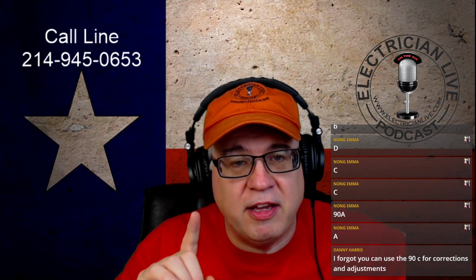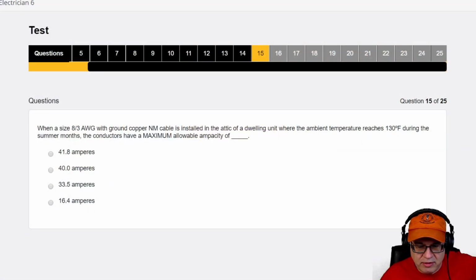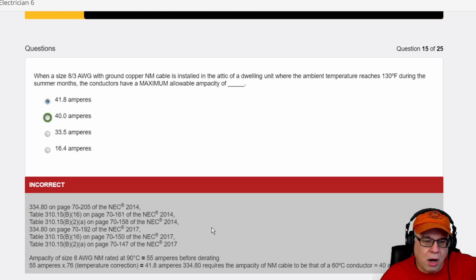Well, 41.8 is my new ampacity. But column C is where my cable's limited to. And as long as it doesn't exceed that, and so 40 doesn't exceed 41.8, that's my new ampacity of the conductor. But I'm still going to be limited in column A, the 60 degree column, because that's what the code says under 334.80 that it's limited to. Okay, so that's kind of a little lesson. So let's go with the 41.8. You see where we're at?